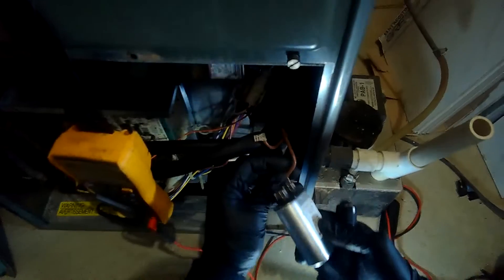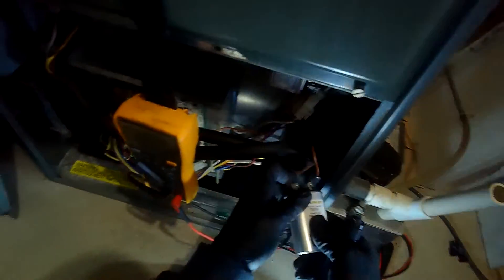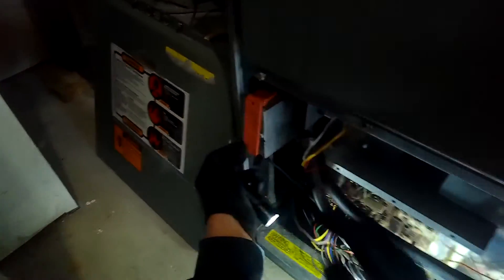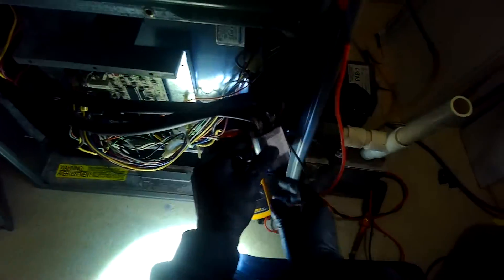Let's see if there's any difference here. I don't think so — they're going to need a new motor. Let's see what happens. The problem is clearances; I don't know if this is going to slide out. Let's get the other meter so I can check the amperage when we start this bad boy up. Oh yeah, let me get the switcheroo. Good old switcheroo — I knew there'd be a time we'd use this bad boy. Look at that, all right. Turn that up, power back on the switcheroo, look at this. Good old switcheroo, Kelvin.